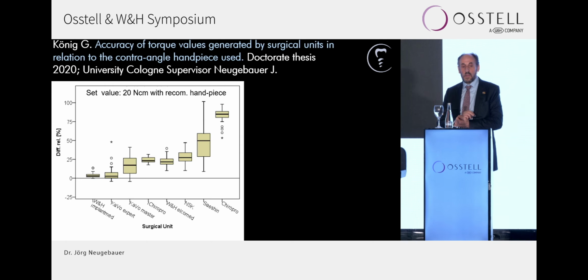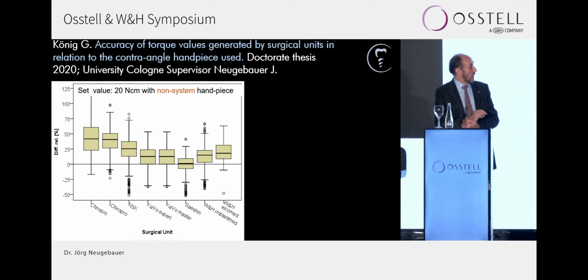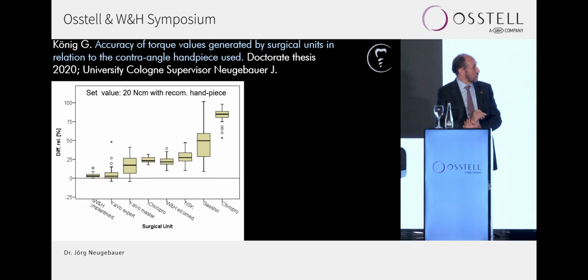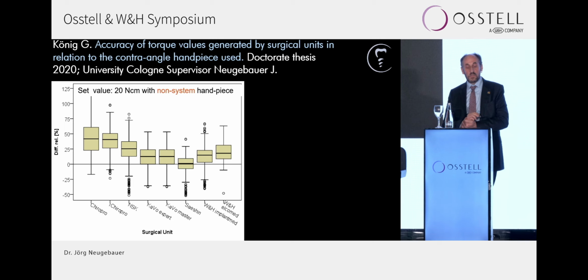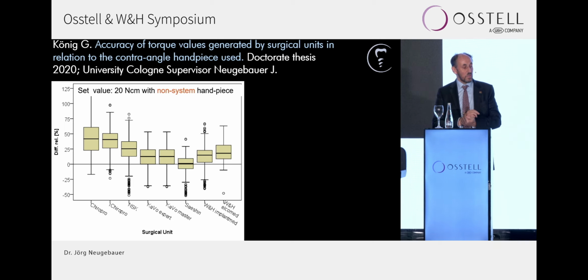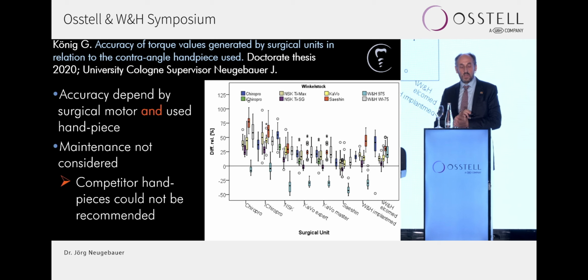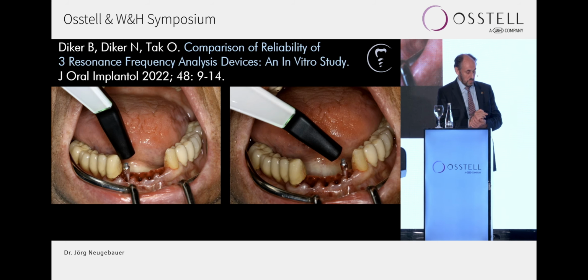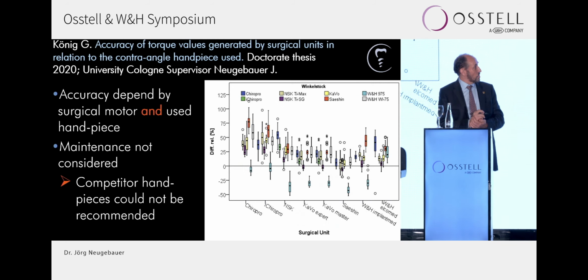We continued this work and did another study on this topic, where a doctoral thesis was done, testing other machines, and we saw even larger deviations, up to more than 50% in these devices, which is also a very high danger. But it becomes more and more complicated if you are using a surgical motor and not the system handpiece, because then the deviations become even more complex, and we saw a large variation. This means that we nearly cannot measure data if we are not staying in the correct system. So we really have to check how the accuracy of the implant insertion torque is determined by the surgical motor and the used handpiece.